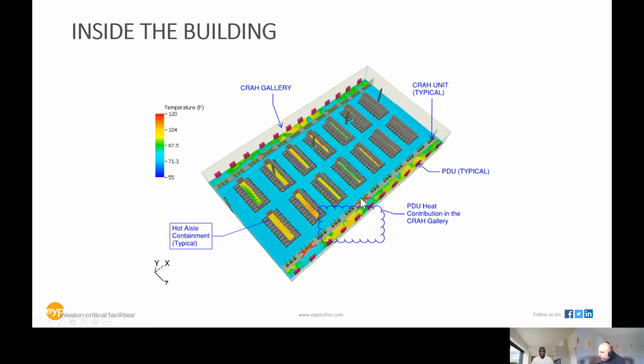So the question I have is, I see 3 X's -- it seems like maybe the units are failing or something. Yes, that's the fail case scenario we're talking about, and I think there are 4 -- the 2 CRAH units with an X on each side have been turned off to simulate an N condition, meaning no redundancy. We do this because at any given time there may be a need to do something with the CRAH unit, like replace the belts, or it fails -- anything can happen. So we want to see what happens in the room. In this case, when all the redundant equipment was turned off, the cooling was still sufficient for the IT equipment.